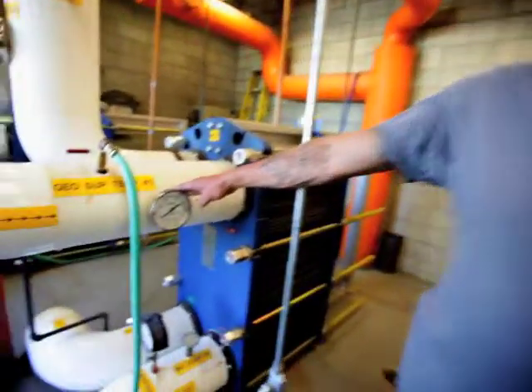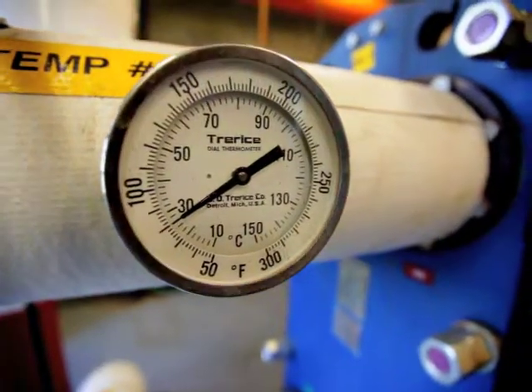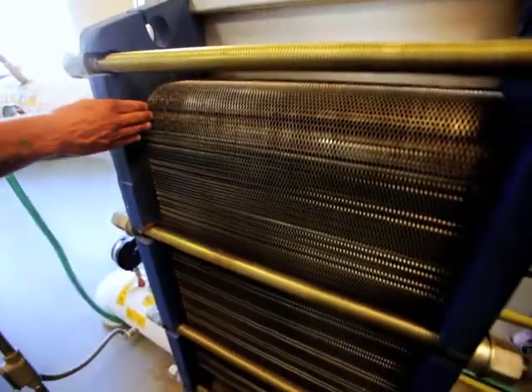This is the supply from the well, and if this were operating, this temperature gauge would be reading somewhere in the neighborhood of 210 to 215 degrees. That water is then circulated through the heat exchanger, and the geothermal water, once it leaves these heat exchangers, is reinjected into the geothermal aquifer so that we're not depleting the resource.